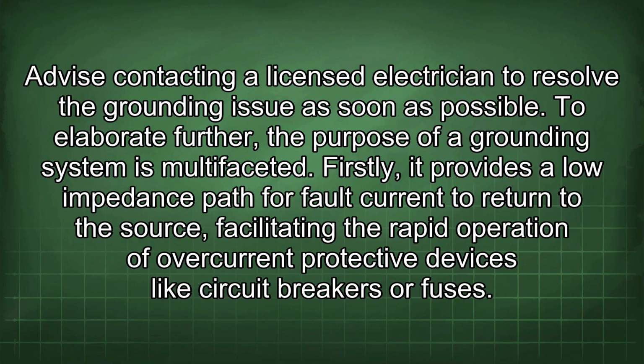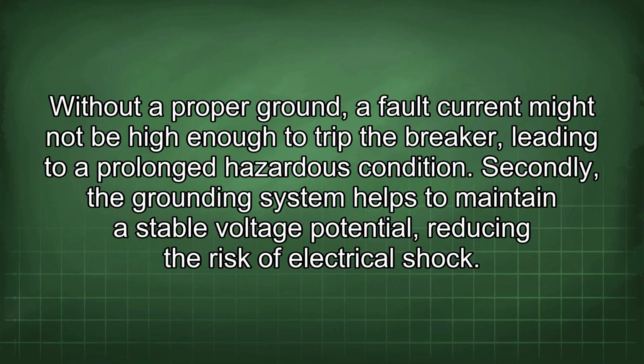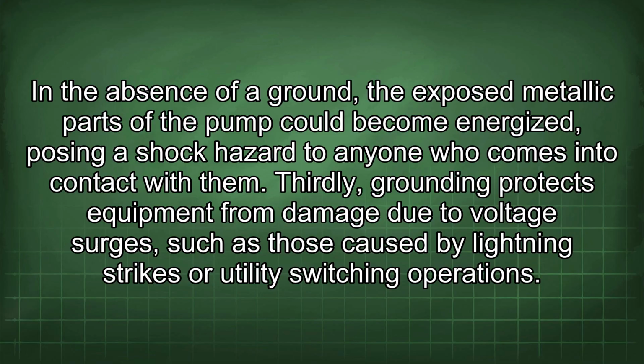To elaborate further, the purpose of a grounding system is multifaceted. Firstly, it provides a low impedance path for fault current to return to the source, facilitating the rapid operation of overcurrent protective devices like circuit breakers or fuses. Without a proper ground, a fault current might not be high enough to trip the breaker, leading to a prolonged hazardous condition. Secondly, the grounding system helps to maintain a stable voltage potential, reducing the risk of electrical shock. In the absence of a ground, the exposed metallic parts of the pump could become energized, posing a shock hazard to anyone who comes into contact with them.